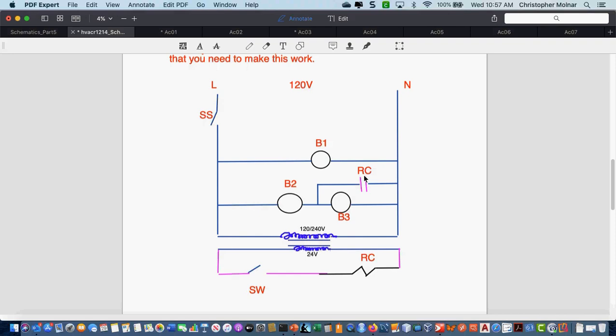Okay, somebody give me the sequence of operation for this diagram. What happens after I close SS and close SW? Tell me what's going on. First, bulbs 1 and 2 are energized with 120 volts. The transformer gets energized, closes the switch, and energizes the coil, which will light up bulb 3.